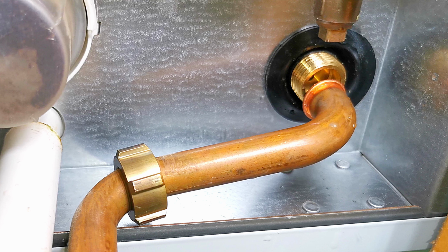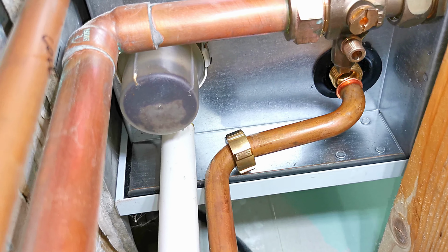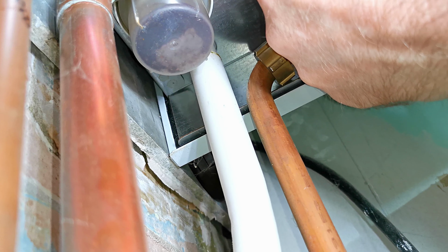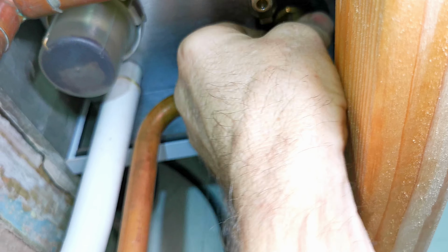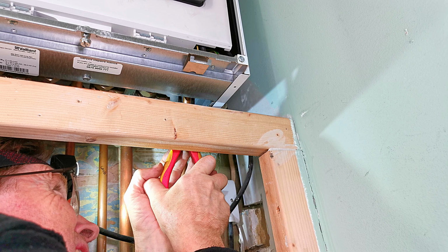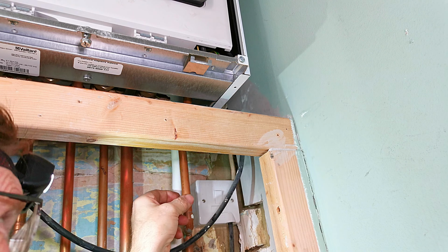I always make sure that the rubber seal that goes around the threads on the expansion relief valve is pushed right up and out of the way. Otherwise it really hinders getting the nut on. Once I've got the nut on, I can then do the nut up finger tight. Then once again I use my long nose pliers just to tighten that nut up. And there we go, we're good to go.